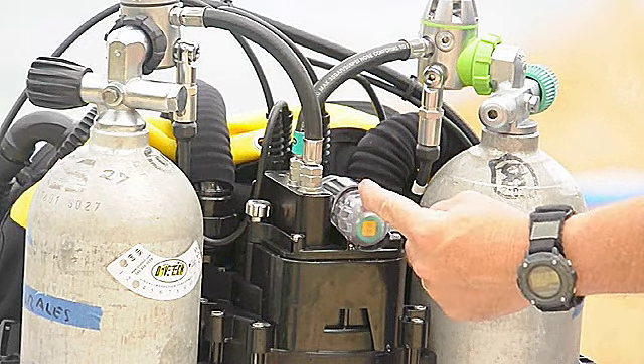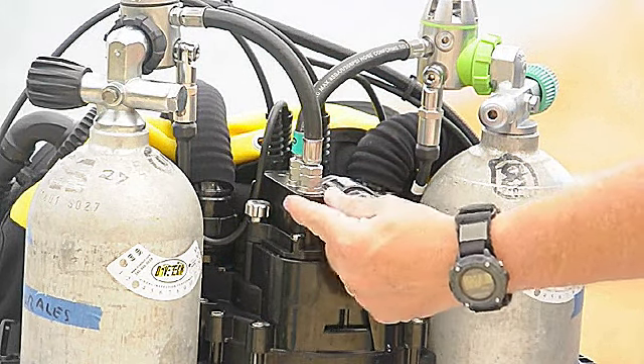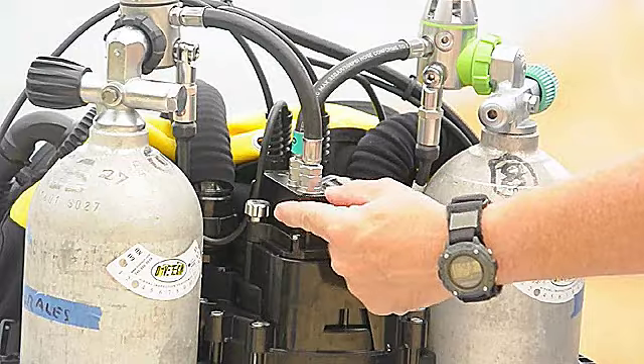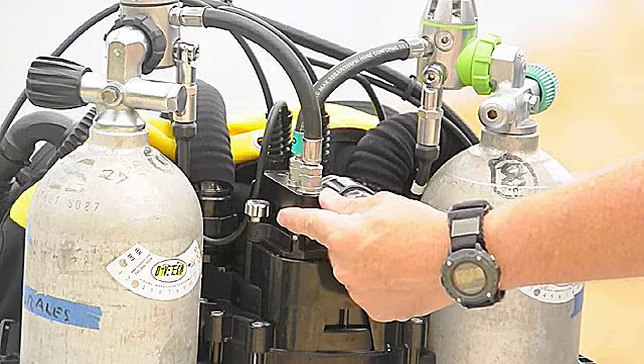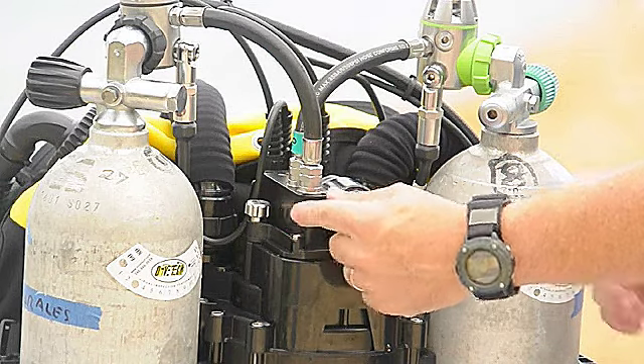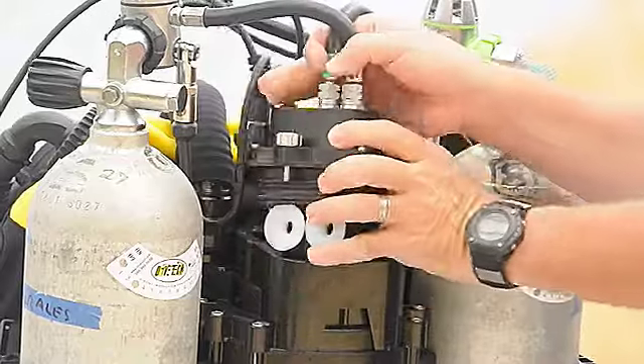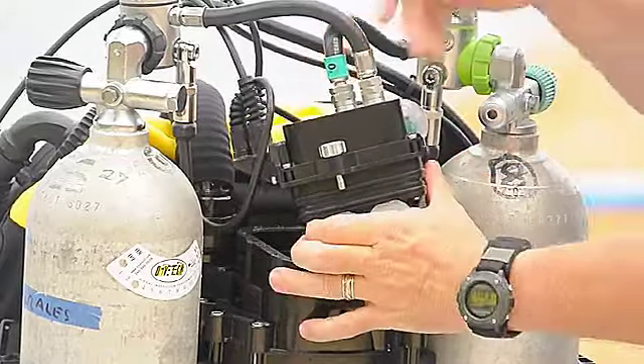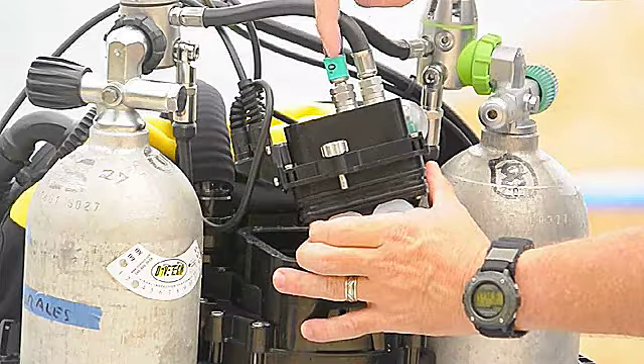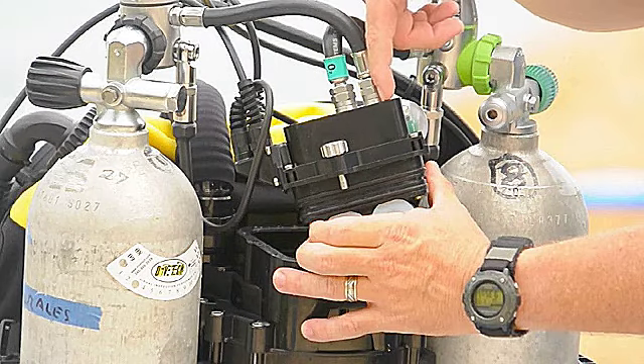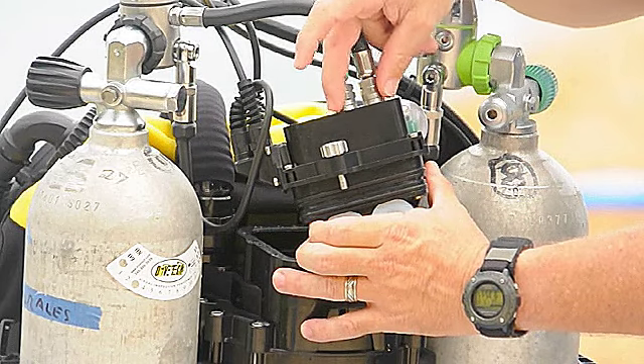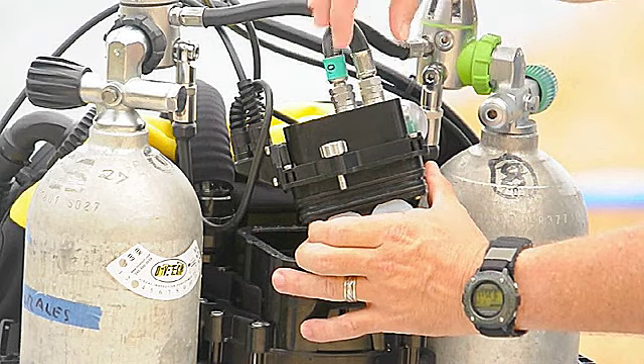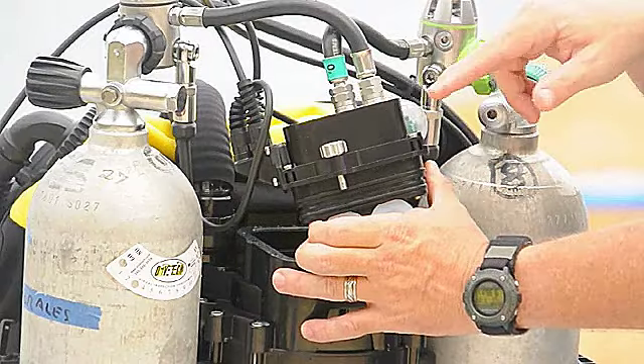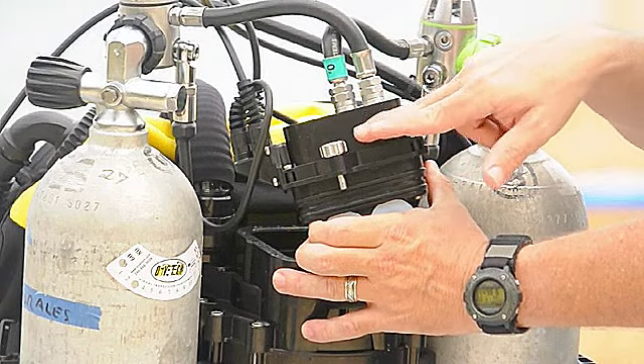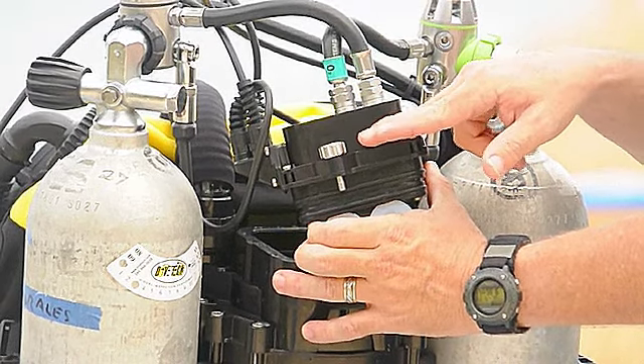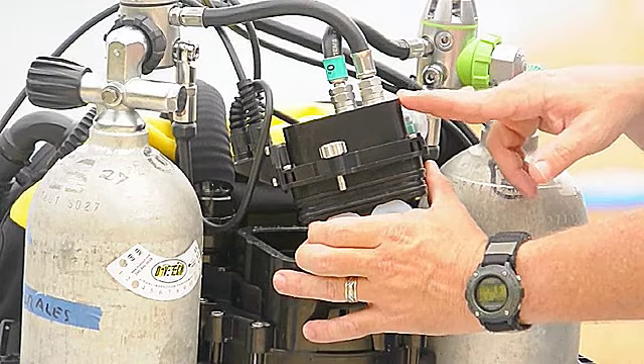So right next to this battery right here is this gas processing module. It's a pneumatics module. It handles all the gas injection to the breathing loop. So I'll pop this module out here, and there are 2 gas supplies to this. One is oxygen, one is air, or whatever your diluent is. And those gases get up into 4 different small solenoid valves that are built into this module. Now, each of those solenoid valves has a very specific purpose.